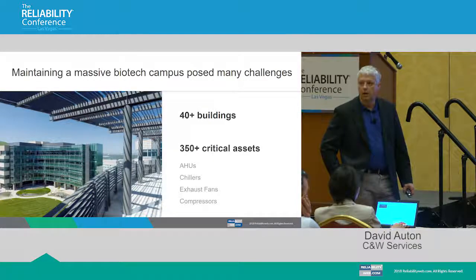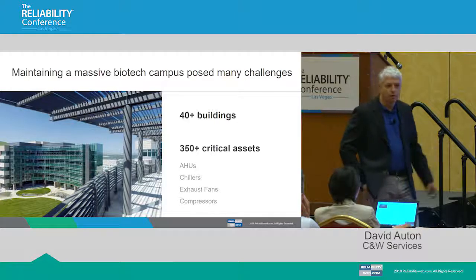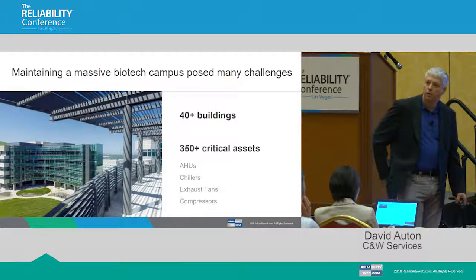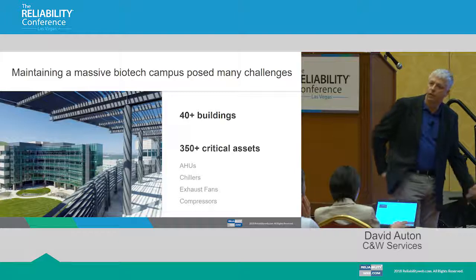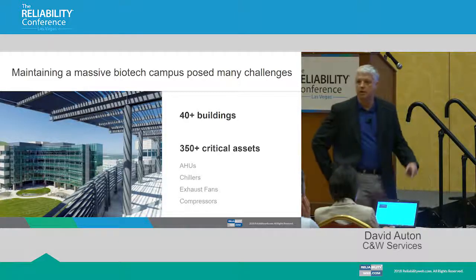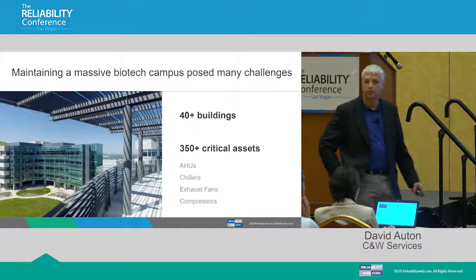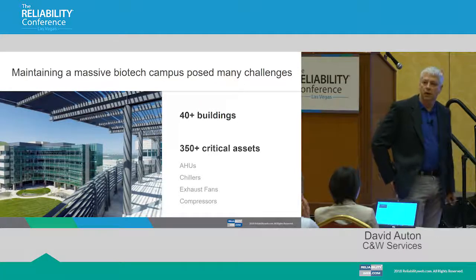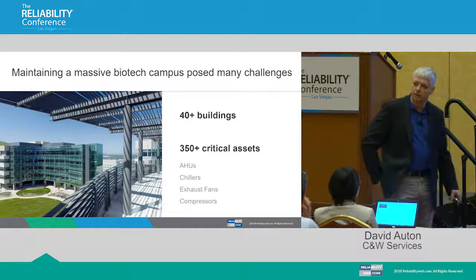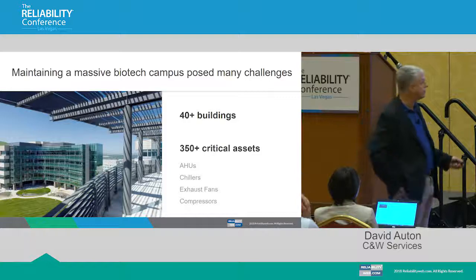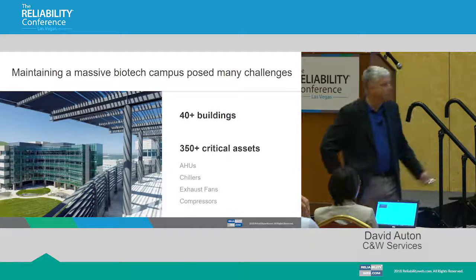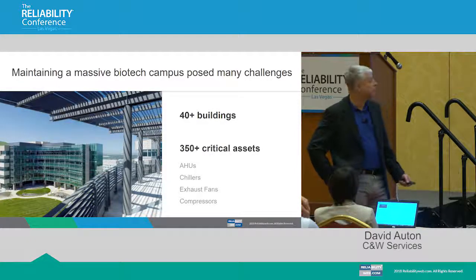If you ever set your controls up wrong with a chiller, and you kick it on for 30, 40 seconds or a minute or two and then shut it off, do that 2 or 3 times and it's not going to start anymore. You really have to run them at 70-80% versus 100% and 0% kind of scenarios. Being able to balance and monitor that was quite a challenge for us.